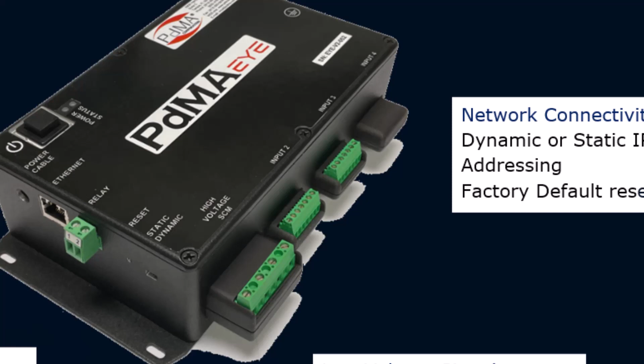It is kind of a different approach for PdMA. Our technology has always been 6-channel, 3 voltages and 3 currents, for the portable EMAX technology. We decided to expand the capability a little bit, recognizing there's a lot of variable frequency drives out there. You've heard us talk about the good, better, best plan. If you can get line side and load side, you're doubling the reliability studies and making sure the drive isn't affecting the distribution system. So with PdMA EYE, you can do line side and load side analysis with the full 12 channels.